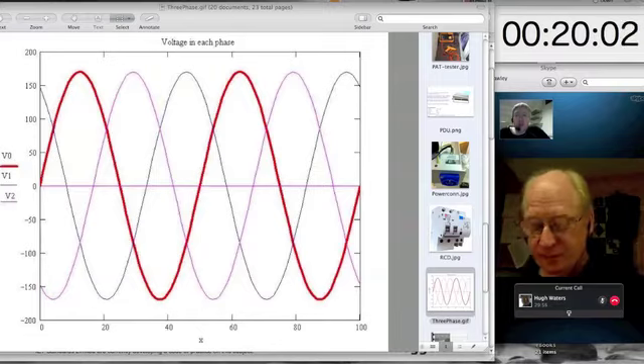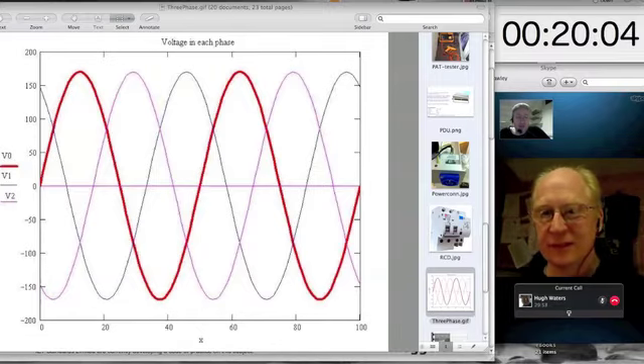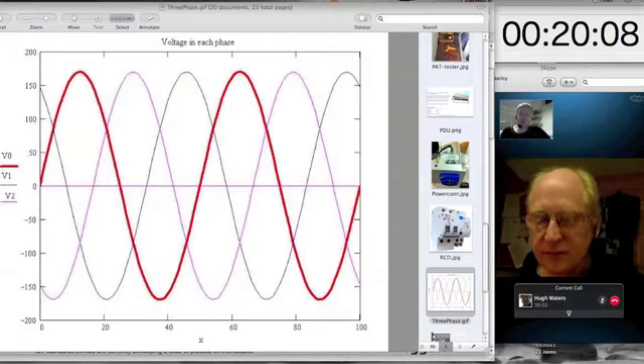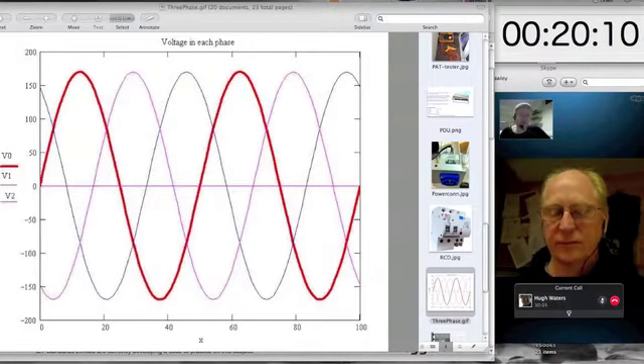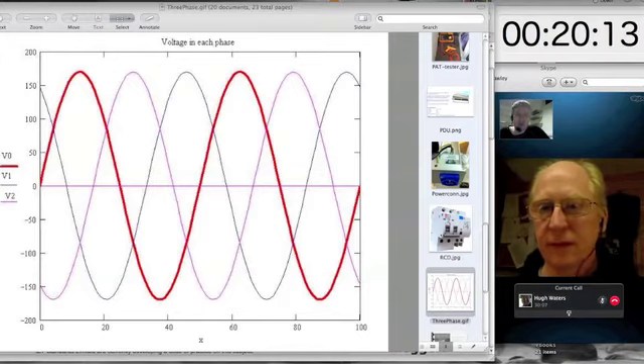So if you have a three-phase incoming feed to your building, the electricity company are not measuring the number of kilowatt hours you're using off each phase and billing you for that. They're saying, which is your most heavily used phase, and we bill you 3 times on that.